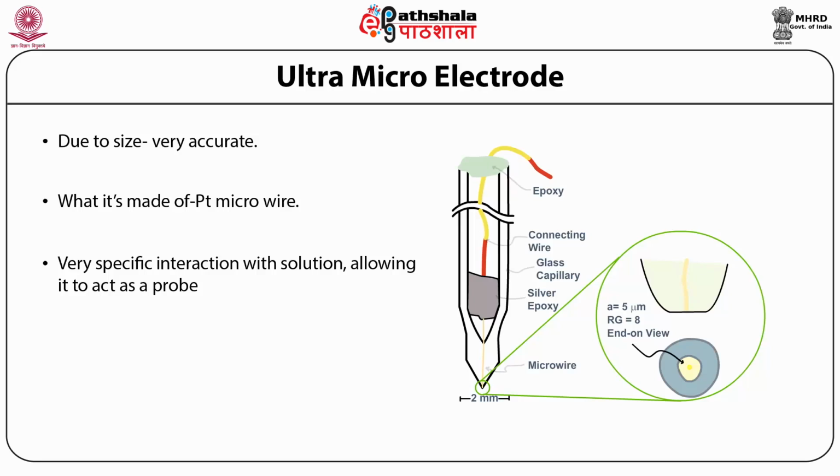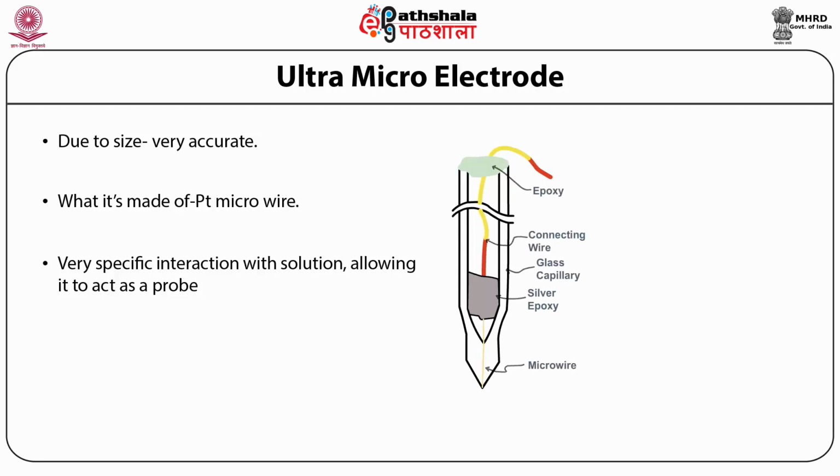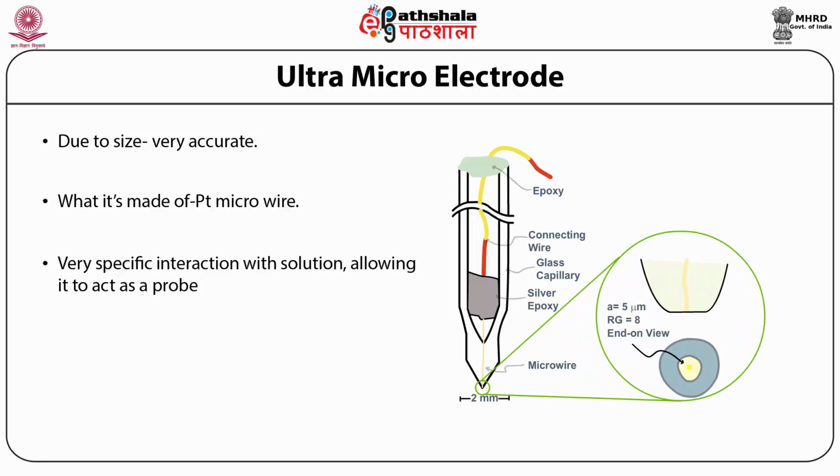Disc-shaped tips are usually made by heat sealing microscopic wire, usually gold, platinum, and carbon, into glass tubes. The end is then polished to expose an embedded disc. The tip must then be ground so that the glass insulator forms a truncated cone.